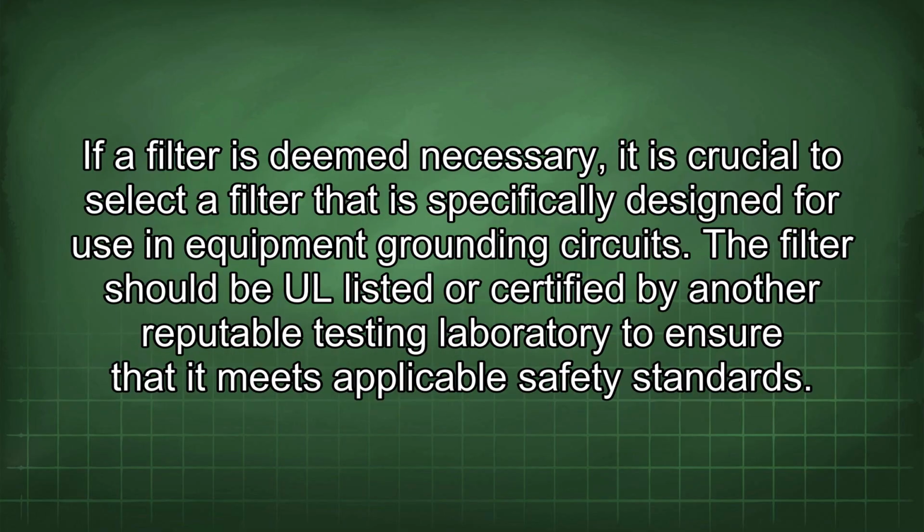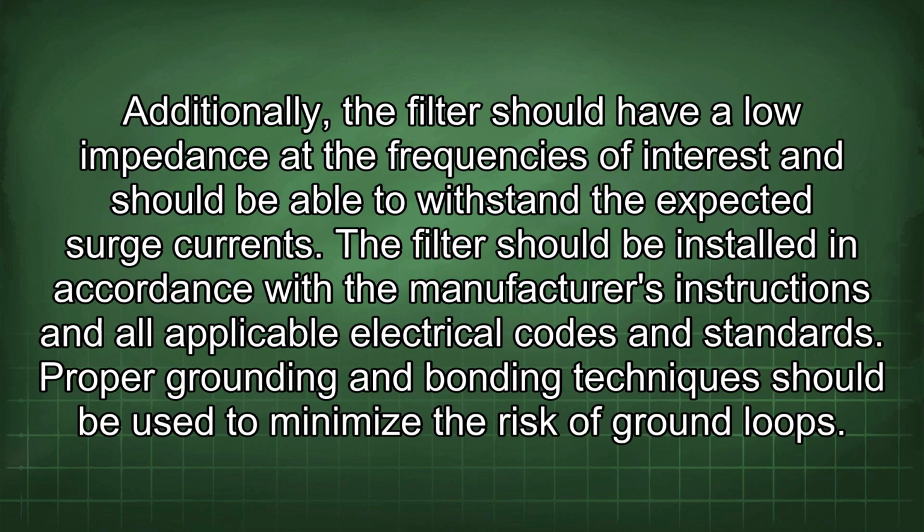If a filter is deemed necessary, it is crucial to select a filter that is specifically designed for use in equipment grounding circuits. The filter should be UL listed or certified by another reputable testing laboratory to ensure that it meets applicable safety standards. Additionally, a filter should have a low impedance at the frequencies of interest and should be able to withstand the expected surge currents. The filter should be installed in accordance with the manufacturer's instructions and all applicable electrical codes and standards. Proper grounding and bonding techniques should be used to minimize the risk of ground loops.